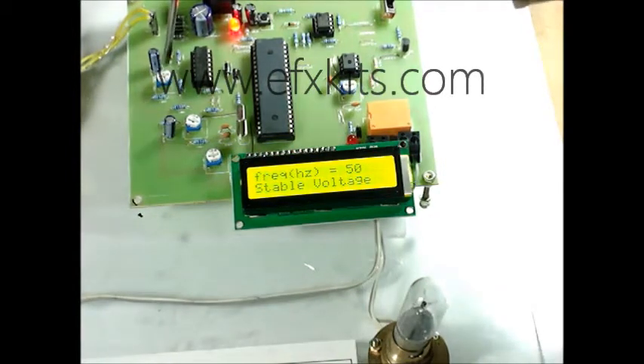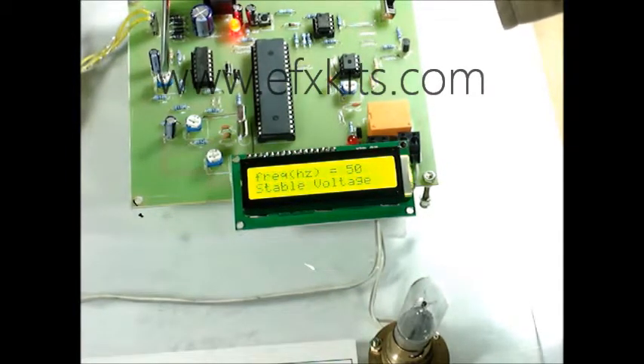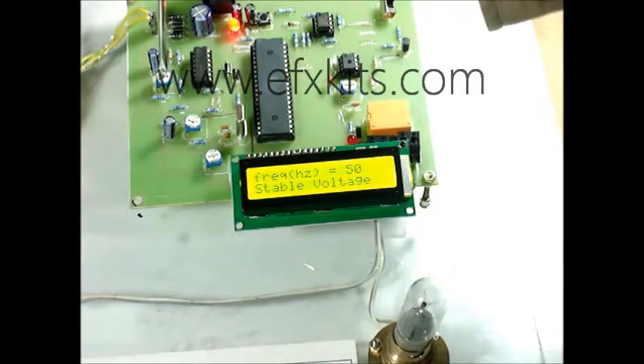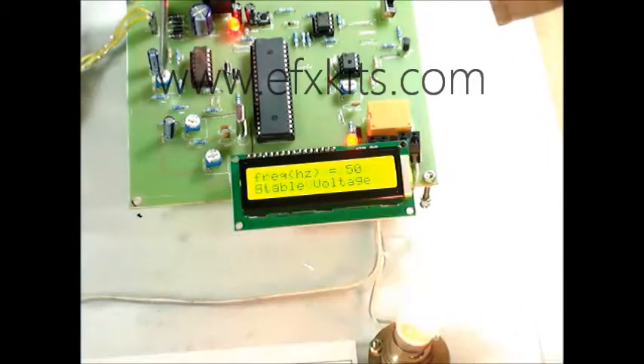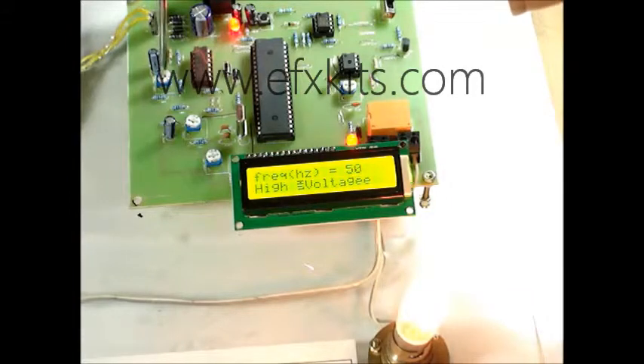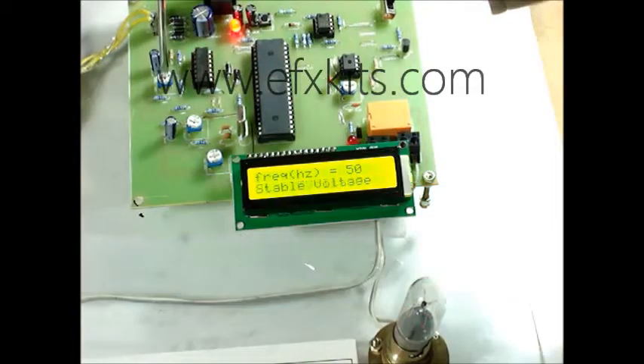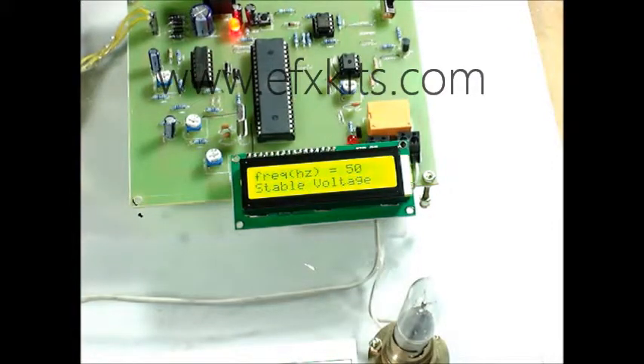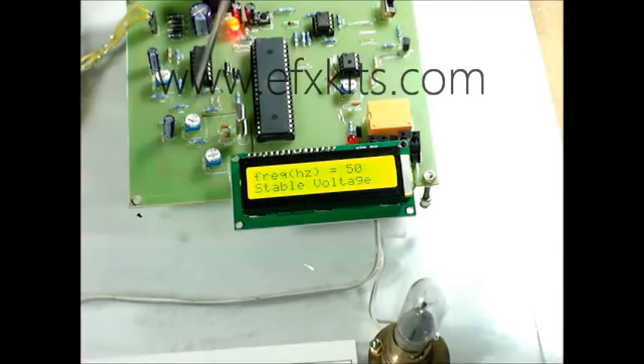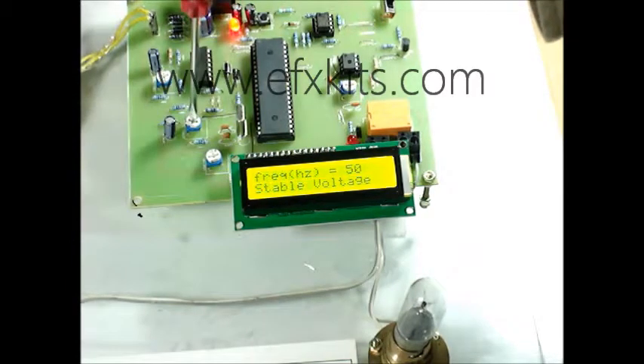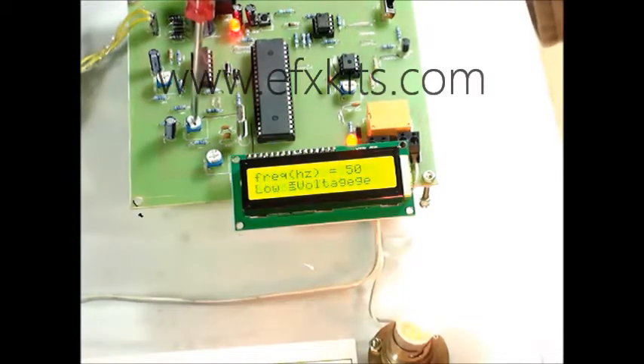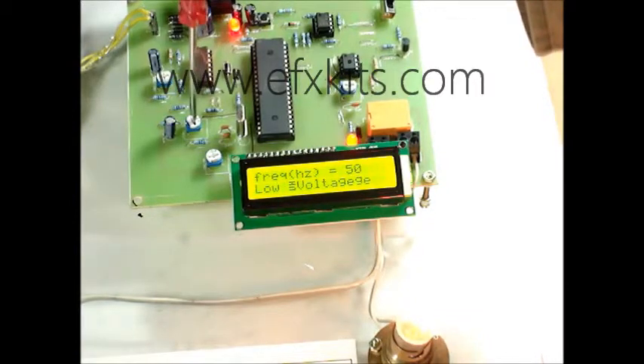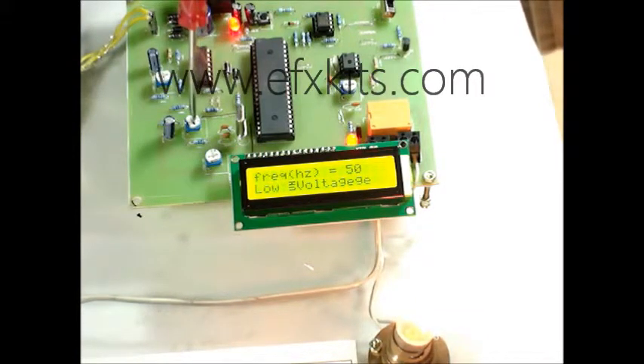Now one of them is the voltage. Now supposing I change the voltage to certain level, now this is high voltage, and the voltage has gone higher, and because the voltage has gone high, islanding has taken place. If the voltage remains normal, the islanding doesn't take place. This is for the higher voltage. This is for the lower voltage. If it falls below the acceptable voltage, it also goes for islanding.